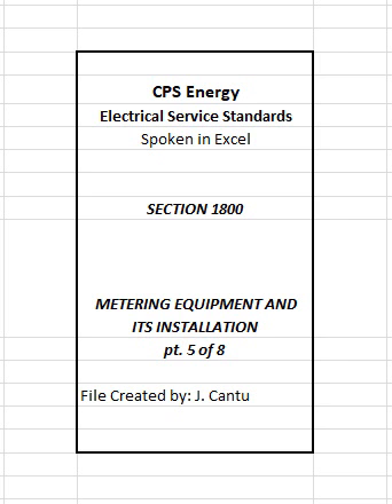1807.5 Clearance from CPS Energy Gas Regulator. Gas equipment shall not interfere with minimum clearances outlined herein for metering and service equipment and shall maintain a minimum horizontal clearance of 3 feet from the gas regulator. Measurement shall be taken from the nearest edge of the electrical equipment to the gas regulator. Additional clearances from windows, vents, and other miscellaneous openings and equipment must also be maintained from CPS Energy Gas Equipment, refer to Figure 1821.